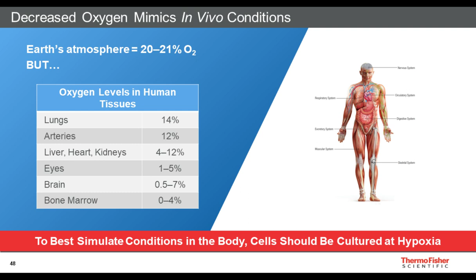Okay, so just like with temperature, I want to provide some tips to maintain gas concentration in whatever incubator you're using. The first, of course, is to check your carbon dioxide calibration at least once a month using a secondary probe or a Fyrite system. Check it first thing in the morning when you get to the laboratory, before the incubator door has been opened and closed throughout the day as people access their cultures. If you're using a hypoxic incubator, check the oxygen concentration first. If you want to do any calibrations, manipulate the oxygen setting before turning to the carbon dioxide, because you're reducing oxygen but adding in carbon dioxide. If you increase the CO2 concentration, that can affect the oxygen measurement.